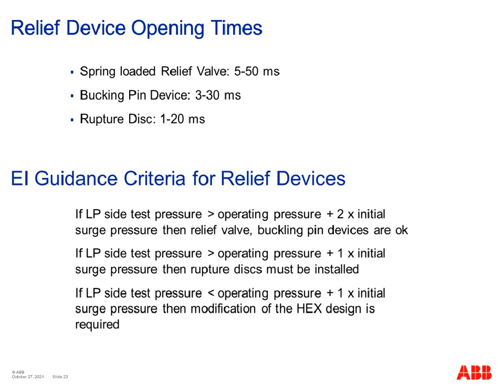So on that, the relief device opening times that are typical. For a spring-loaded relief valve, they would open in 5 to 50 milliseconds typically. A buckling pin device, which is another type of relief device, which you don't see very often, they're a bit old-fashioned, 3 to 30 milliseconds for those. And for a rupture disc or a bursting disc, you're thinking about 1 to 20 milliseconds for these. So that's quite an improvement on the relief valve, and that improvement can make all the difference in terms of relieving the pressure that would otherwise build up in the exchanger and possibly cause it to catastrophically fail.